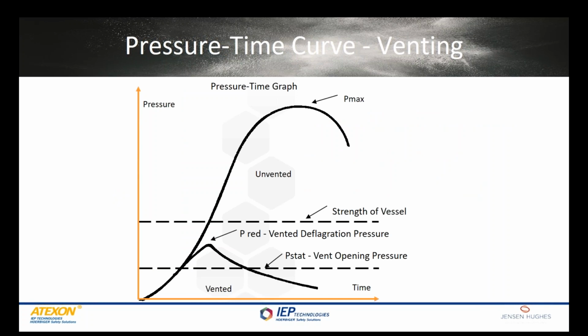This is a pressure time curve for explosion venting. A couple of things to keep in mind on this. The whole purpose for the explosion vent is to make sure that we keep the reduced pressure after venting below the vessel strength so that we don't see rupture or deformation of that vessel. The other thing I'd like you to take away from this particular graph is there's two separate values specific to the vent. And the first is P-stat.